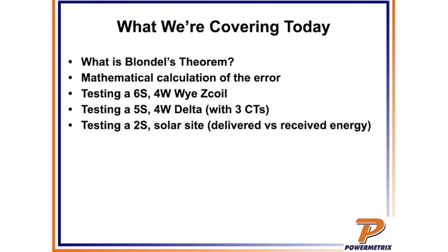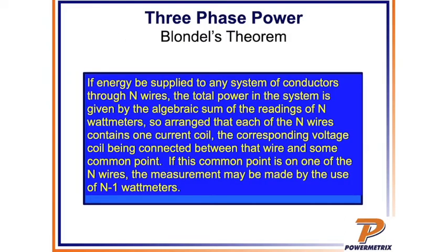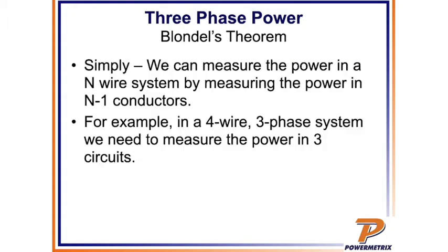Hey everyone. We're going to talk a little bit about what is Blondel's theory? What does it have to honor and what would be a violation of Blondel's theorem? So what the heck is it? So by the letter of the law, Blondel's theorem is if energy be supplied to any system of conductors through N wires, the total power of the system is given by the algebraic sum of the readings of N watt meters. So arranged that each of the N wires contains one current coil, the corresponding voltage coil being connected between that wire and some common point. If this common point is on one of the N wires, the measurement may be made by the use of N minus one watt meters. What does that mean in English? Does anyone understand what the heck that means?